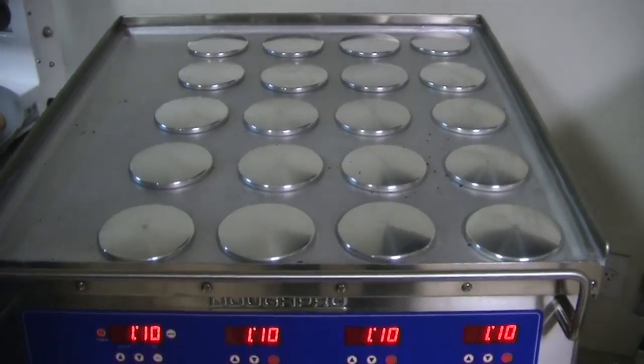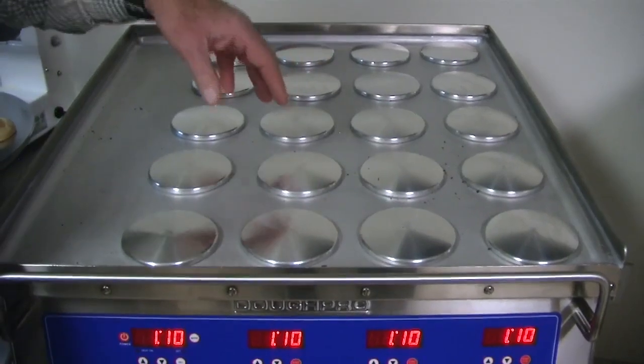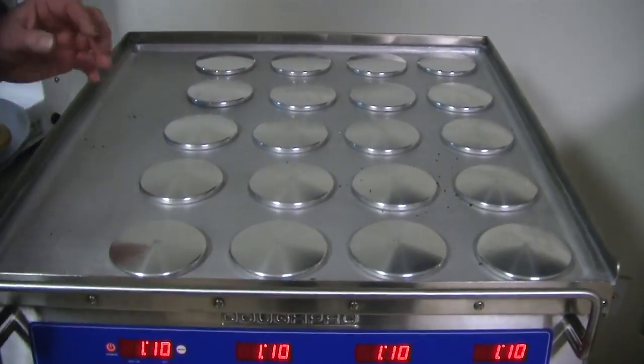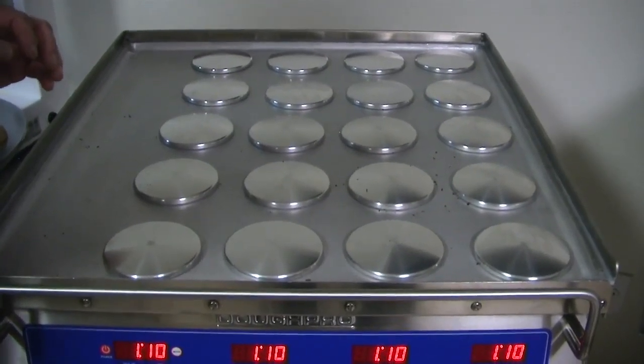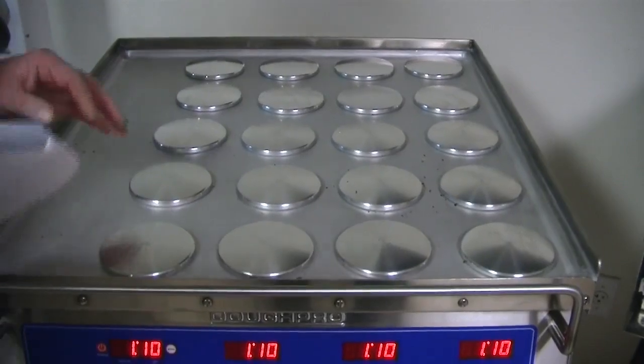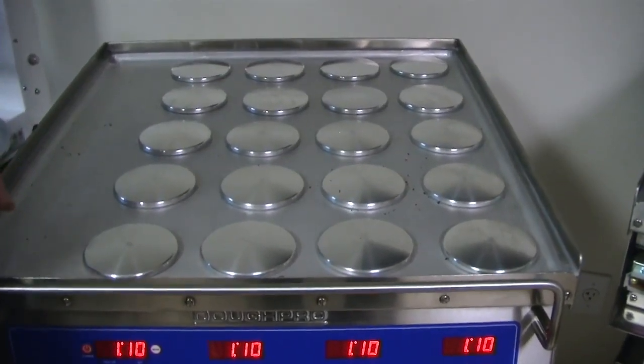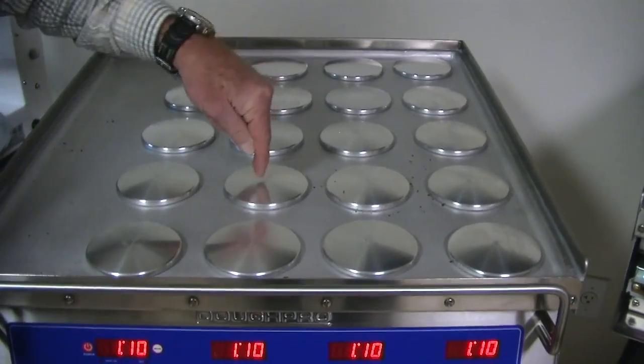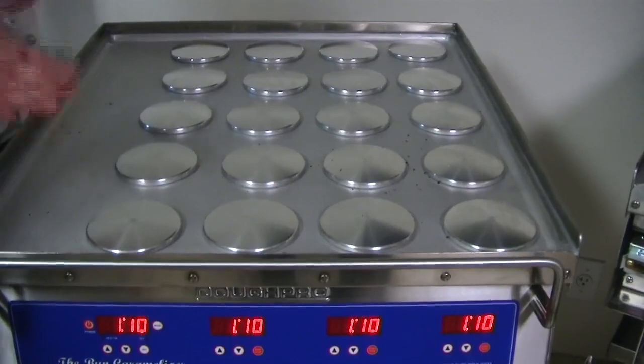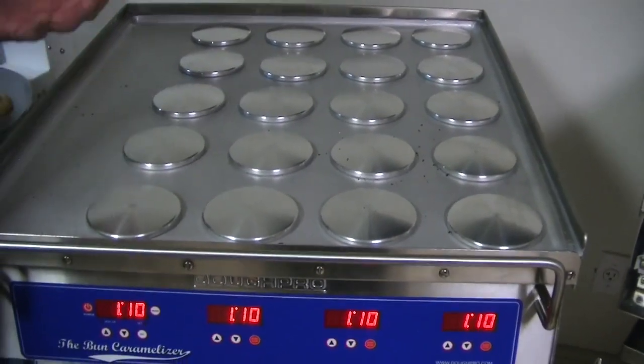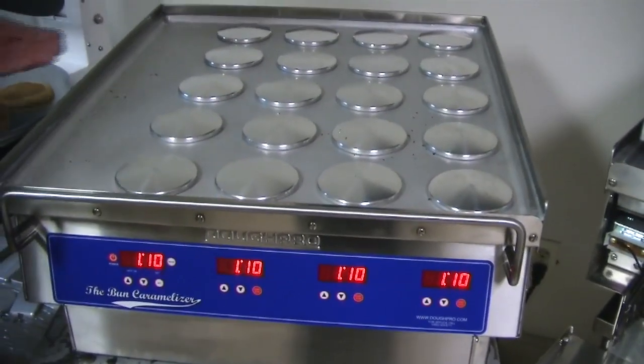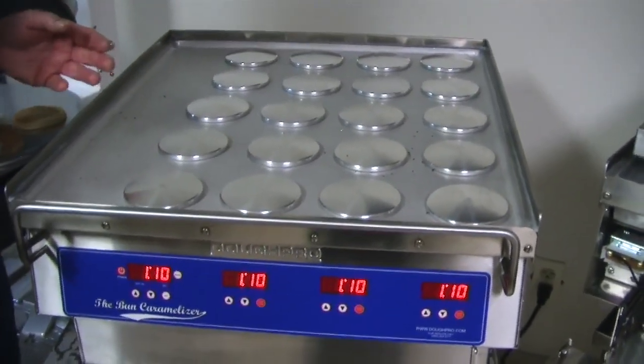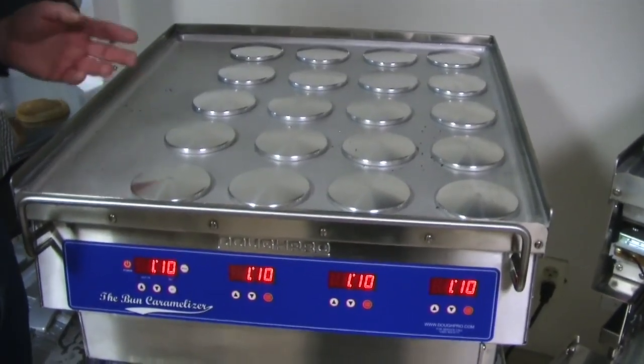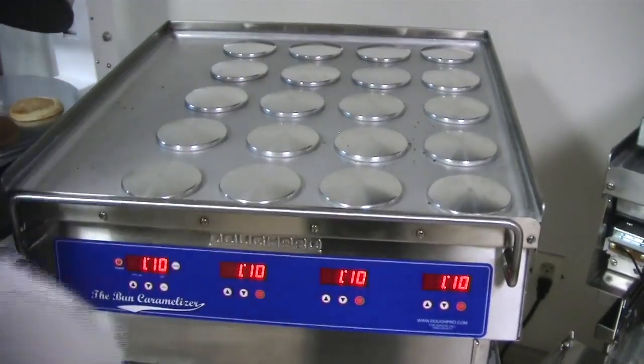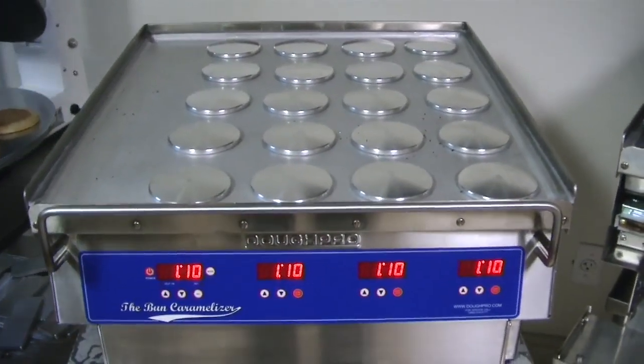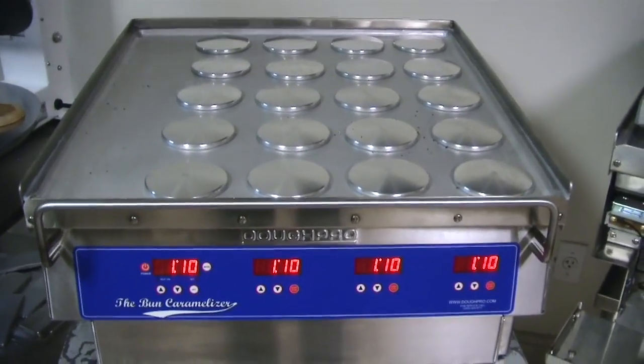If the outer or inner perimeter, the outer zone or the inner zone, labeled Zone 1, Zone 2 in here, is not heating, there's an offset function, if it's as simple as calibrating. We calibrate from the surface here to here, and we calibrate with an offset to get that temperature either up or down, and 99.9% of the time we're going up, which is a negative number on the offset, to bring that temperature up. You might make sure that that's not causing a problem, just simple calibration. And we recommend you call customer tech support to learn exactly how to set the offsets internally inside the controller.